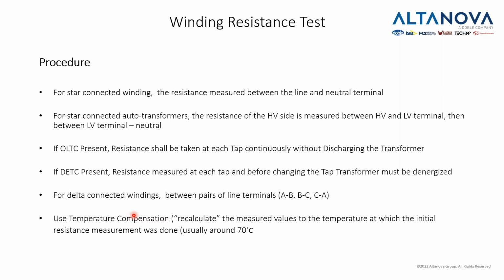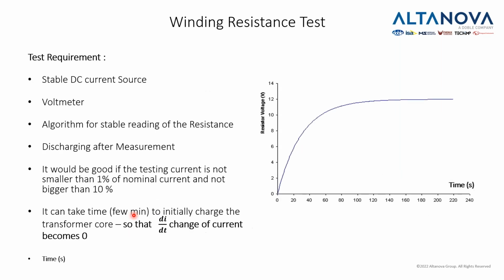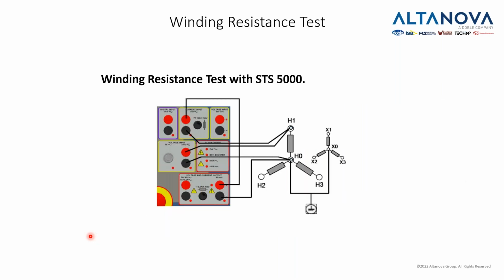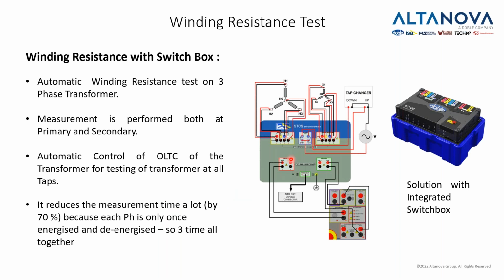So our test sets have that automatic temperature compensation. So we can see here that in time, the voltage will stabilize. The current will actually reach the desired value. We need to wait until di/dt becomes zero so that we can measure R. And this is how we would connect. We would generate a current and measure a voltage drop. And in doing so, we would be able to do that step by step.